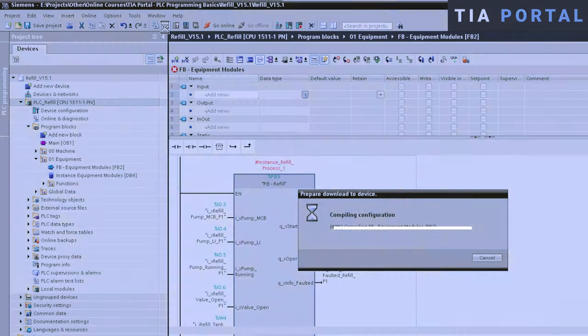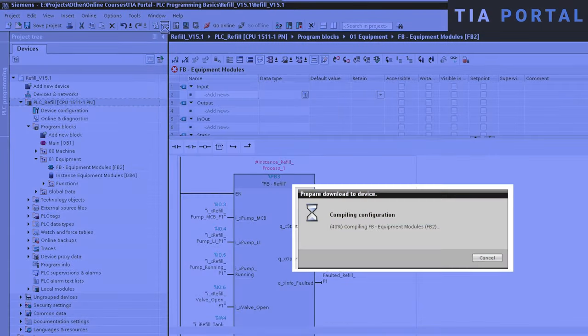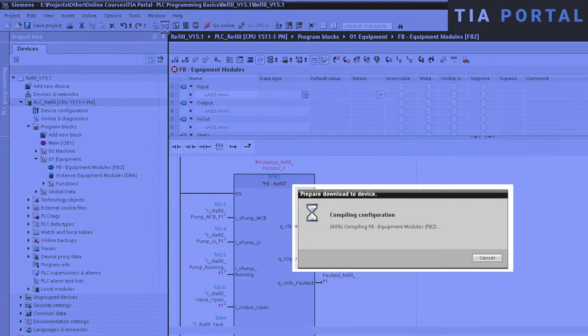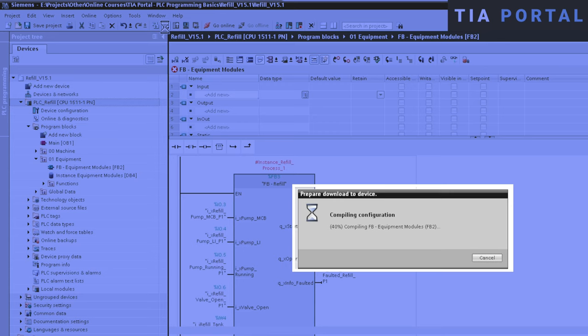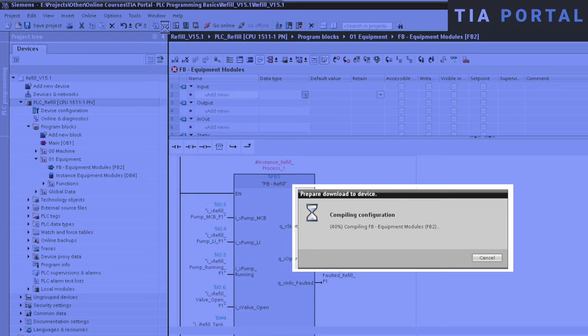If we just pause the video for a second, you can see that TIA Portal is automatically compiling all blocks before the download. Whenever you want to download changes to the interface of a function block in TIA Portal, you don't need to worry about the consistency of your blocks, because TIA Portal automatically compiles your whole application before each download. And during this compilation, all block calls are automatically updated if needed. Amazing stuff!